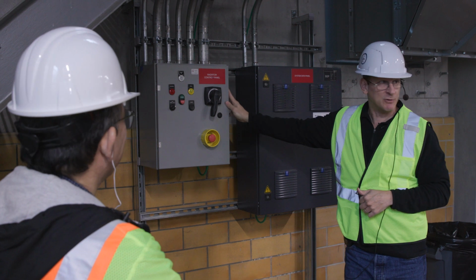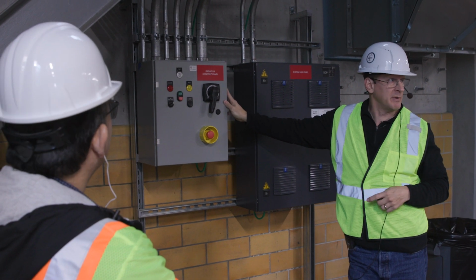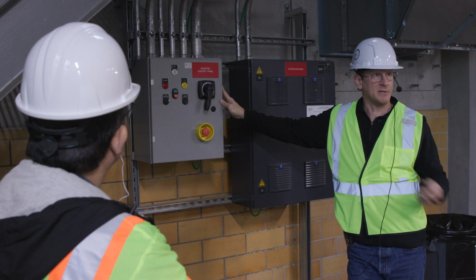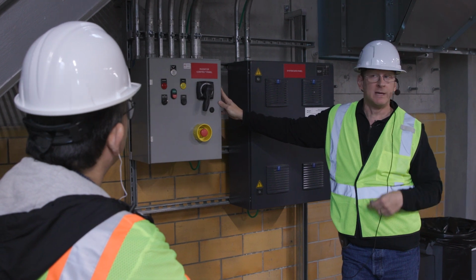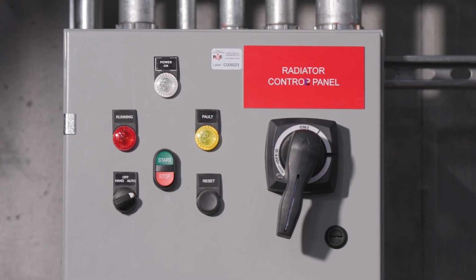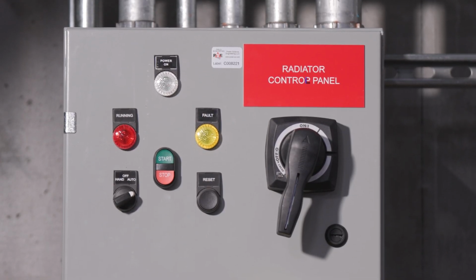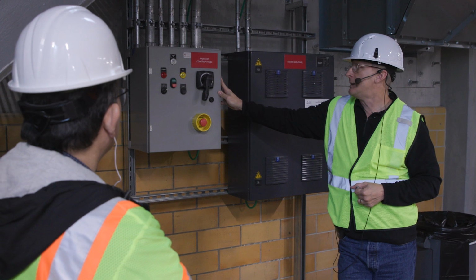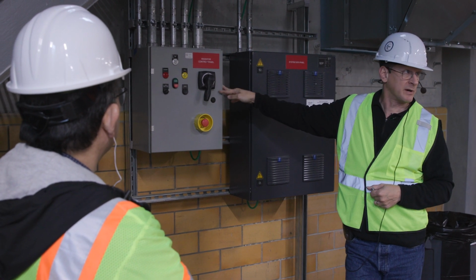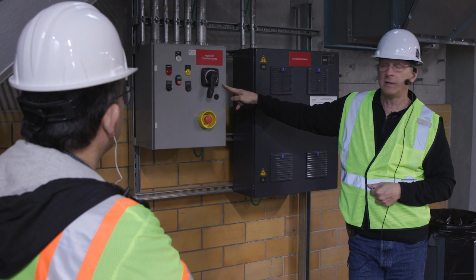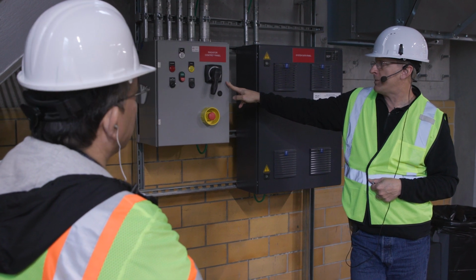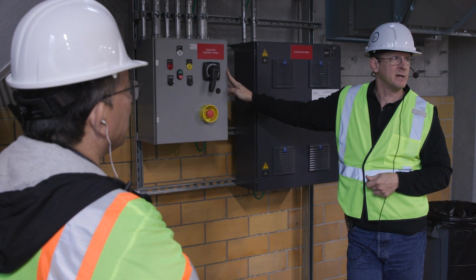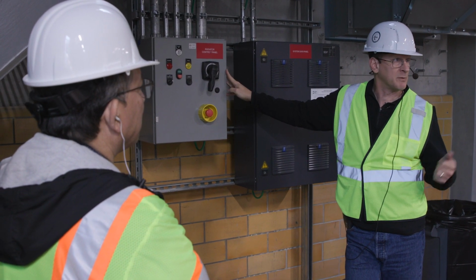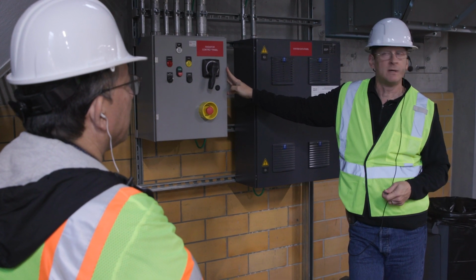This is the actual panel that turns the radiator on and off. So we communicate with this panel as well through our PLC. We give it an engine run signal, and then it will basically close the contactor to send voltage to the radiator up top and run the radiator. It is a soft start. There is a soft start in here for the radiator motor, with all the requisite protections for the motor itself, and feedback into our PLC for alarms and so forth.